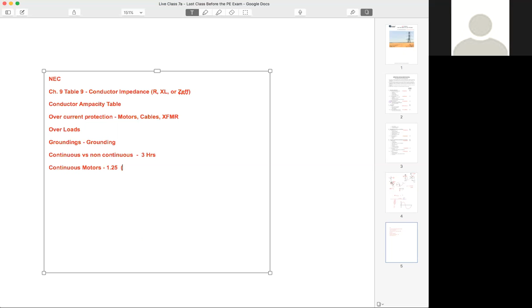Know how to size continuous motor loads. What do you multiply your full load amps by? Yep, 1.25. Is that multiplier for your breaker or for your conductor? Conductors, awesome, great job. What do we size the breaker off of? Is the breaker protecting the cable or protecting the motor? All good things to think about.